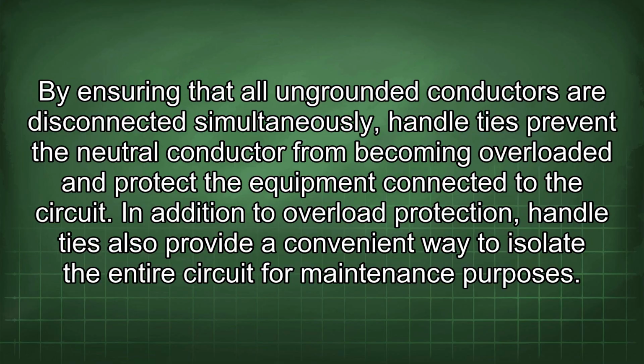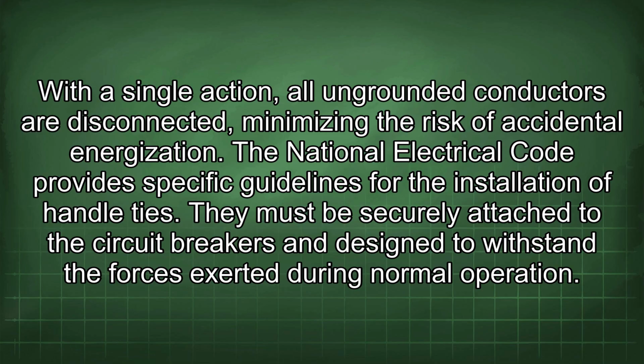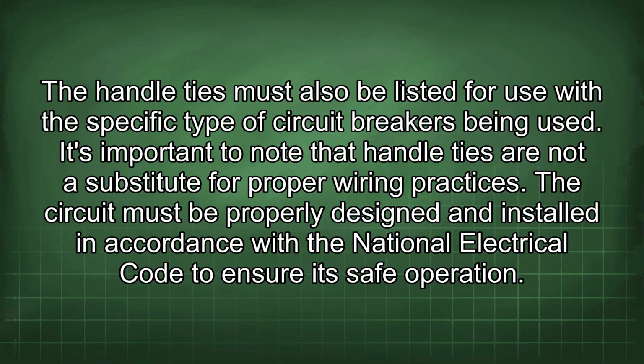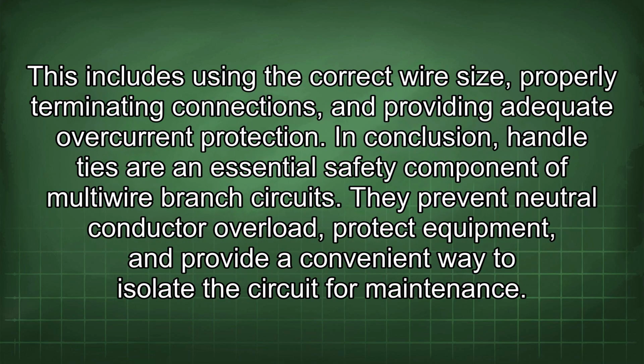In addition to overload protection, handle ties also provide a convenient way to isolate the entire circuit for maintenance purposes. With a single action, all ungrounded conductors are disconnected, minimizing the risk of accidental energization. The National Electrical Code provides specific guidelines for the installation of handle ties. They must be securely attached to the circuit breakers and designed to withstand the forces exerted during normal operation. The handle ties must also be listed for use with the specific type of circuit breakers being used. It's important to note that handle ties are not a substitute for proper wiring practices. The circuit must be properly designed and installed in accordance with the National Electrical Code to ensure its safe operation. This includes using the correct wire size, properly terminating connections, and providing adequate overcurrent protection.